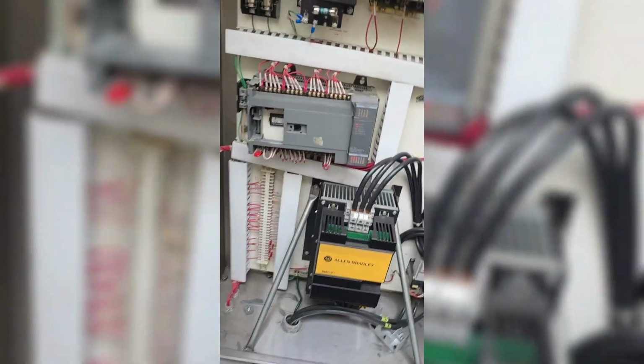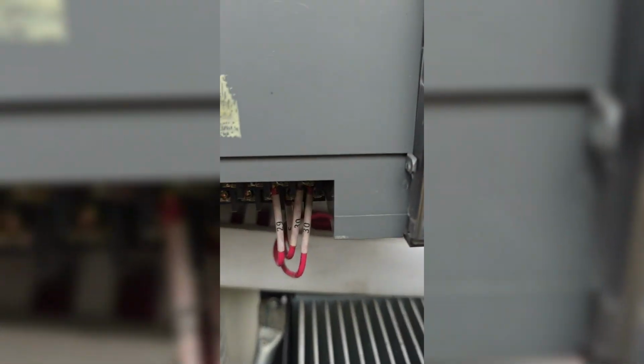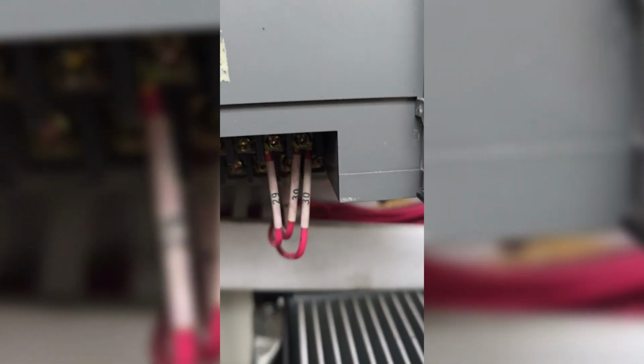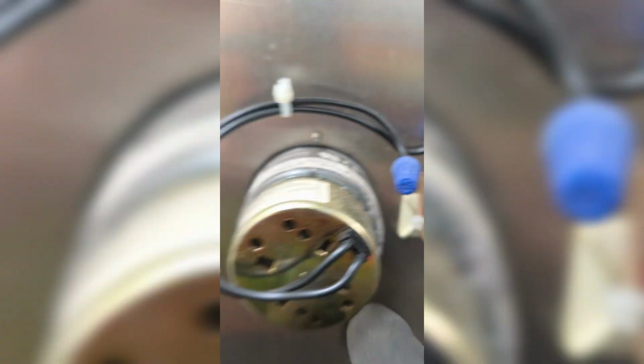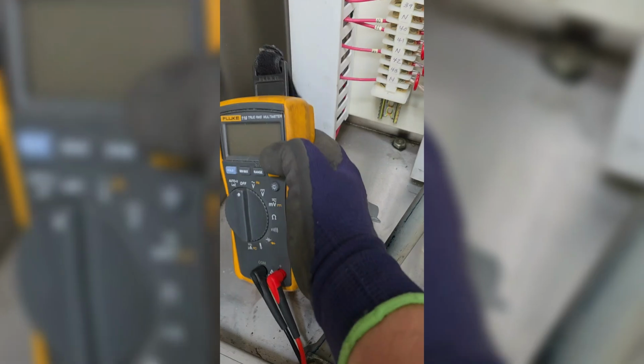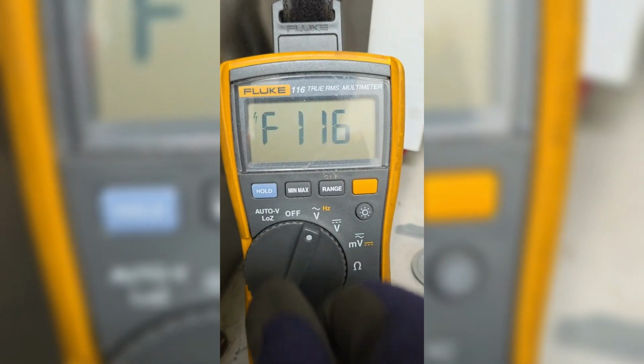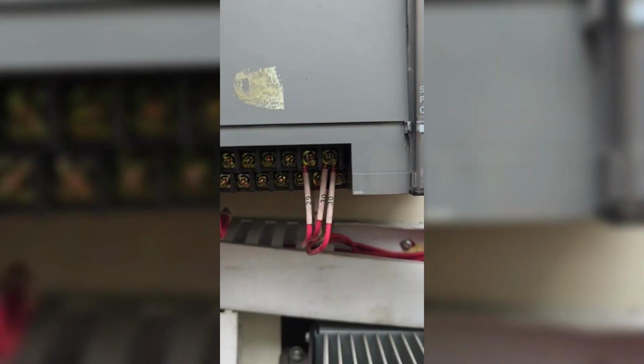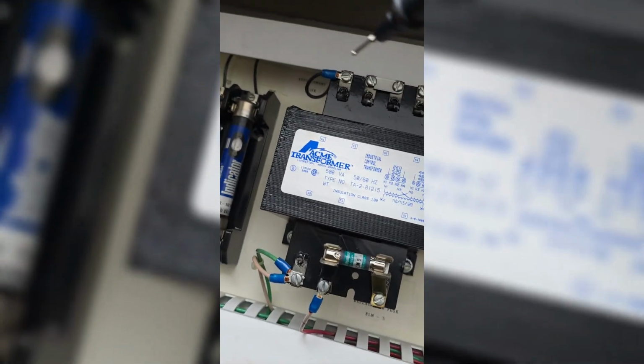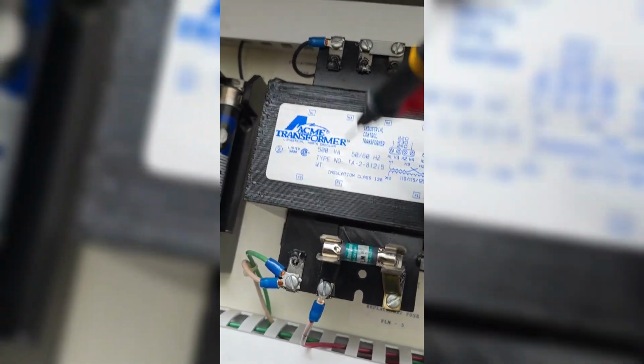All right, so now we're inside of the electrical cabinet, and boom, what do I see right there? Wire number 30. It's also wire number 30 that's feeding the backside of our hours meter. So now I'm gonna use my multimeter, grab my probes, and get to probing. I'm gonna set my meter to 120 volts AC, since this is a 120 volt circuit. And our 120 volt circuit is coming right off of this step down transformer. 480 volts in, 120 volts out.